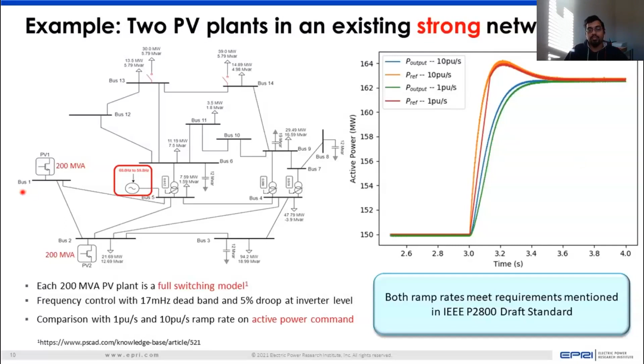The moment you put this in a weak network, and we went to the bookend minimum or bookend weak network perspective, what we did was we just disabled the infinite bus. So everything now becomes a 100% IBR network for the same system that you saw on the previous slide. All that was done is disable the infinite bus at 2 seconds. And you see that although 1 per unit per second seemed to be a reasonable response in the strong network, it's unstable, or it's unable to take that transition when you go to a weak network.